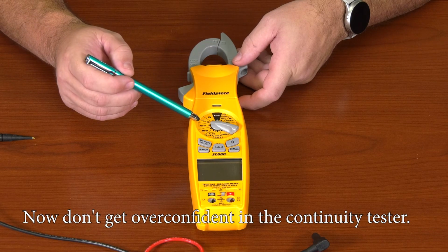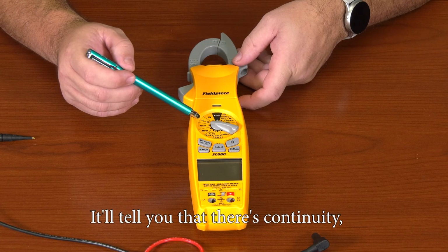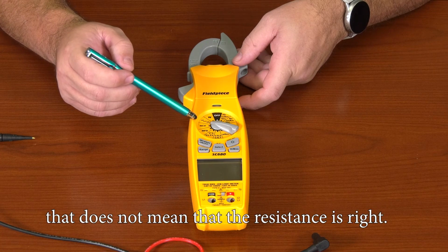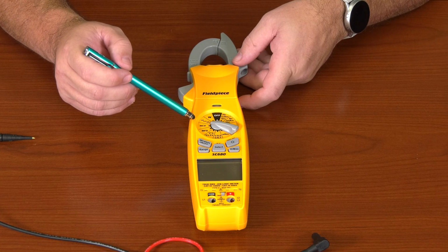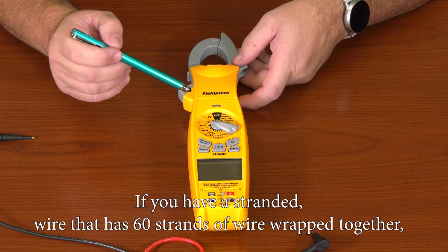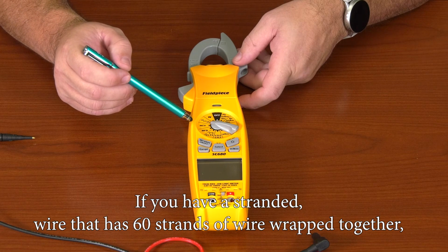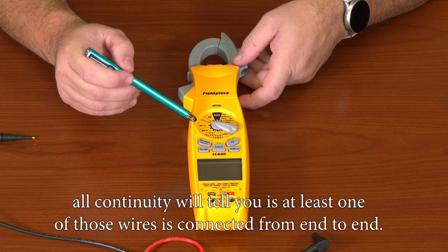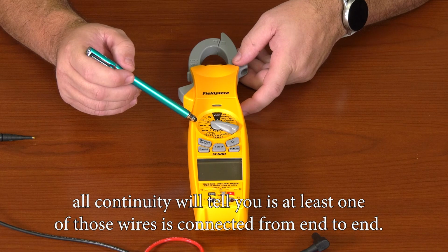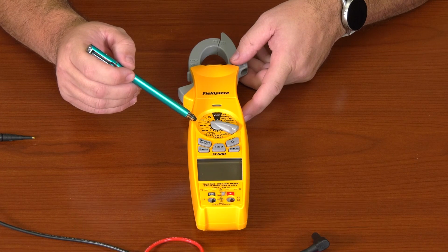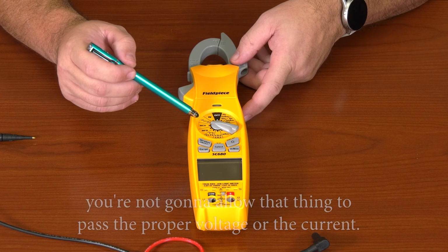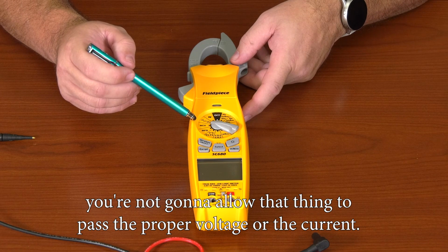Now, don't get overconfident in the continuity tester. It'll tell you that there's continuity. That does not mean that the resistance is right. If you have a stranded wire that has 60 strands of wire wrapped together, all continuity will tell you is at least one of those wires is connected from end to end. If the other 59 are broken, you're not going to allow that thing to pass the proper voltage or the current.